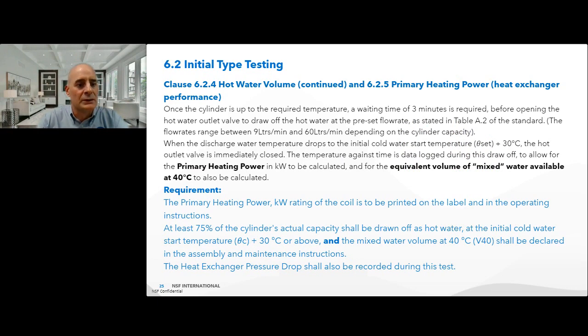Before opening the hot outlet valve to draw off the hot water at a preset flow rate as stated in Table A2 of the standard. The flow rates range between 9 litres a minute and 60 litres a minute depending on the cylinder capacity. When the discharge water temperature drops to the initial cold water start temperature, theta set plus 30 degrees, the hot outlet valve is immediately closed.